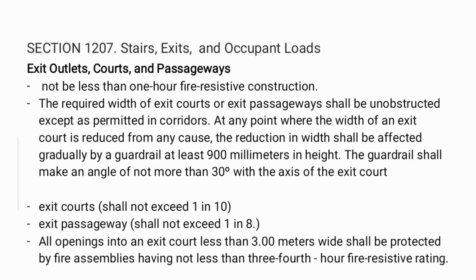And of course, pertaining to its slope, the slope of the exit courts should not exceed 1 in 10, and the exit passageway should not exceed 1 in 8 ratio. And then all openings into an exit court less than 3 meters wide shall be protected by fire assemblies having not less than three-fourths hour fire-resistive rating.